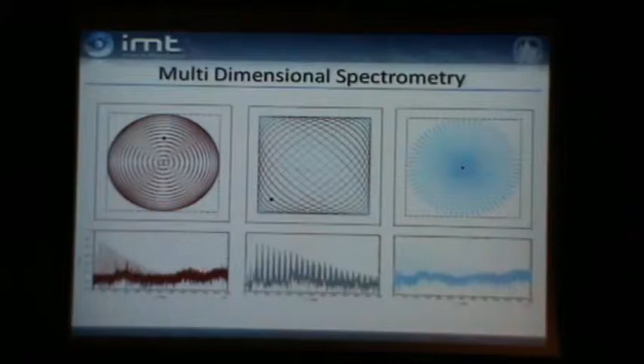Okay. Then to imagers. The first imager I would like to introduce is the asymmetric coil topology. Here, a design published in 2009 by Timo Sattel, one of our alumni. What is the idea behind? When you have this conventional design of having here in the vertical direction the combined selection field and drive field coils, and here in the horizontal direction another pair of drive field coils, then even today we have a problem of the confinement in between the coils. So the measurement field is very small. We have only preclinical scanners today.